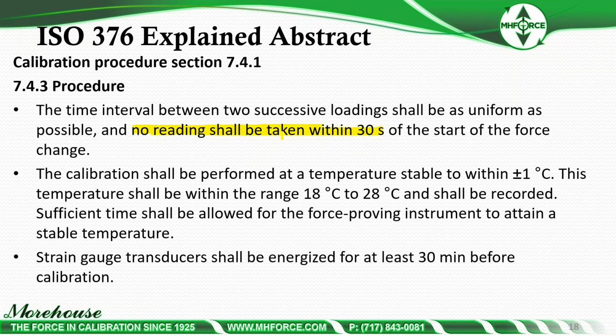ASTM does not address this. We've adopted for all of our calibrations, because it's just general good measurement practice, to take at least a dwell time of 30 seconds and then start taking the readings, especially with static force.